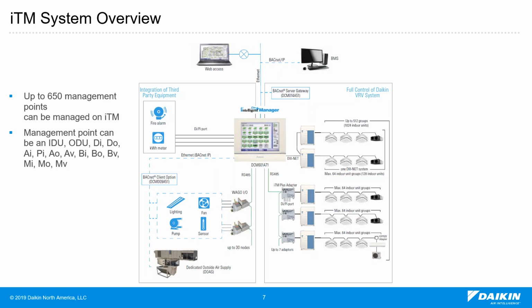So this is the architecture of the ITM, and its capability to integrate to the VRV system using the ITM plus adapter, or directly through the D3net port. And on the left-hand side is the integration with different equipment in the building, like fan, lighting, pump, dedicated outside air supply system. All of those can be tied into the ITM through the Wago IO or through BACnet IP. And also, if there is a BMS on the side at the job site, you can add the ITM BACnet server gateway function. Then the ITM will act as a gateway. So that's an overall view of the architecture of the ITM.